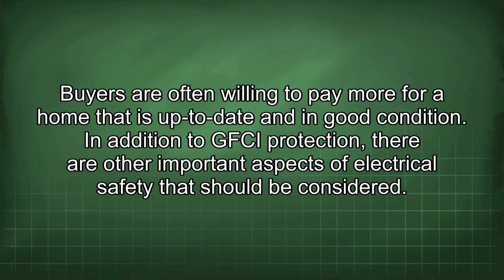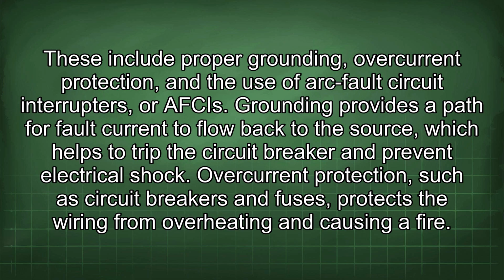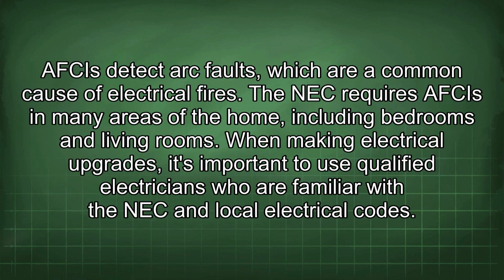In addition to GFCI protection, there are other important aspects of electrical safety that should be considered. These include proper grounding, overcurrent protection, and the use of arc fault circuit interrupters, or AFCIs. Grounding provides a path for fault current to flow back to the source, which helps to trip the circuit breaker and prevent electrical shock. Overcurrent protection, such as circuit breakers and fuses, protects the wiring from overheating and causing a fire. AFCIs detect arc faults, which are a common cause of electrical fires. The NEC requires AFCIs in many areas of the home, including bedrooms and living rooms.